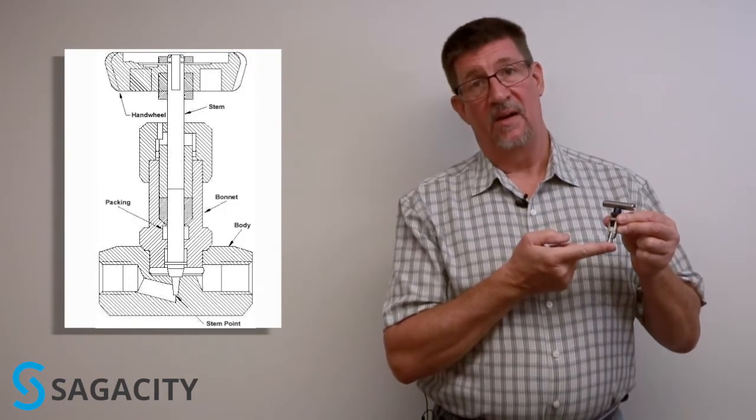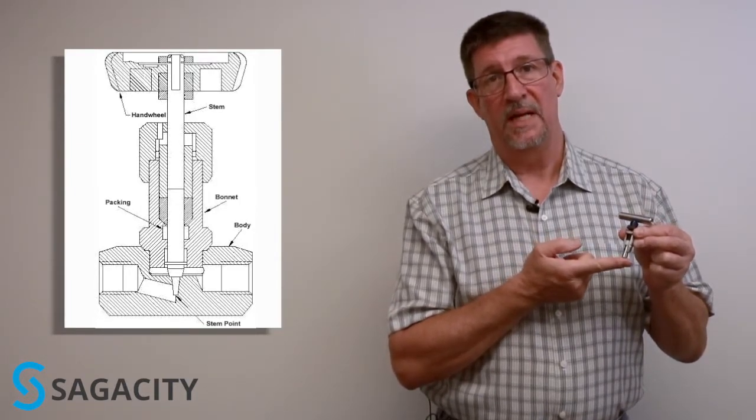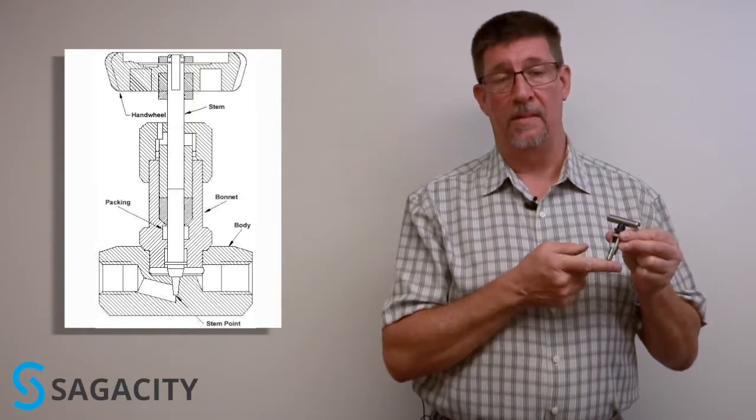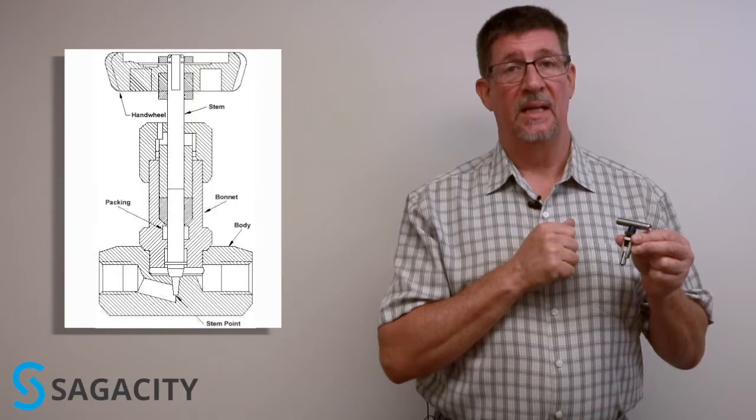and base valve needle assembly. In this particular case, it's a non-rotating stem, which has a little ball, a rotating ball, and a knuckle joint down here so that it doesn't wear the metal seat in the body when it's tightened down.